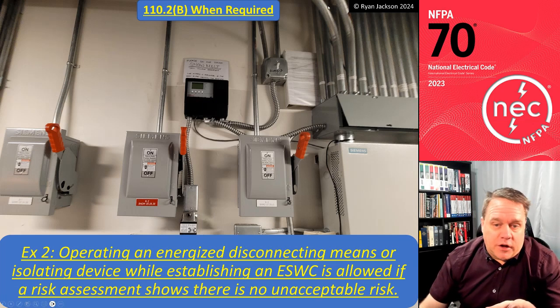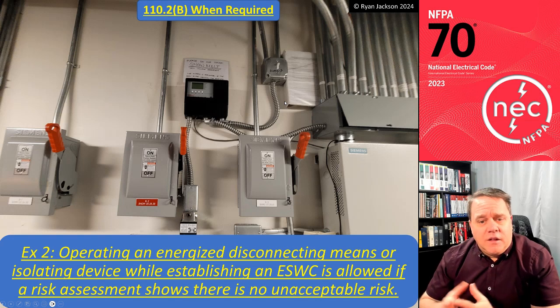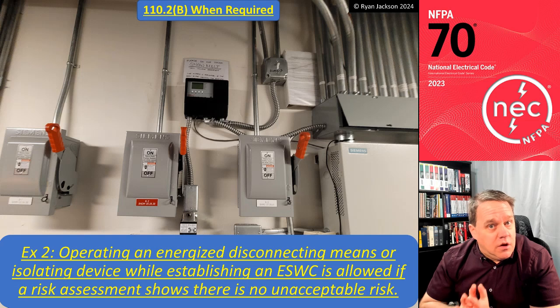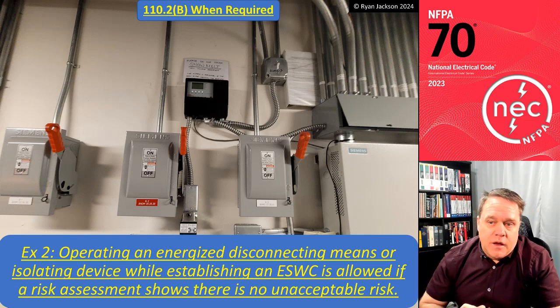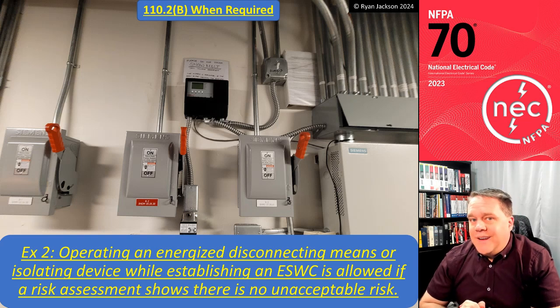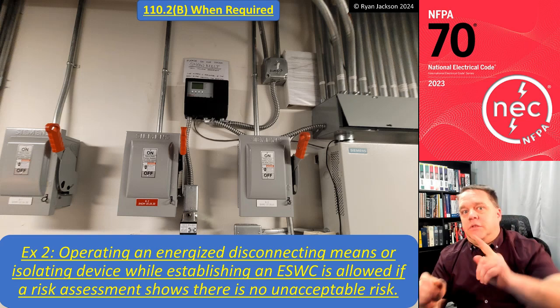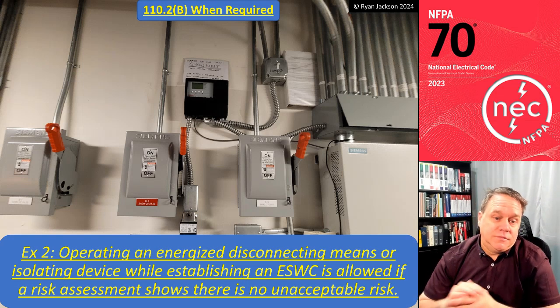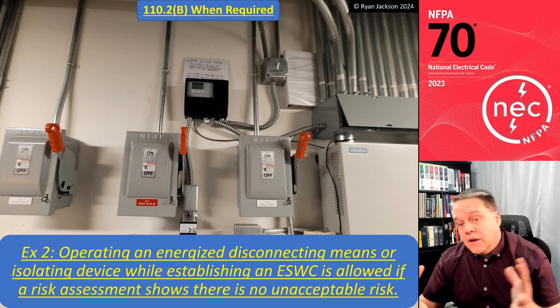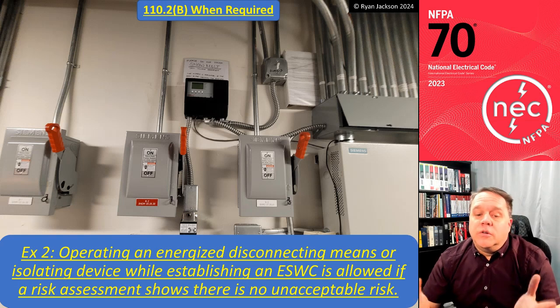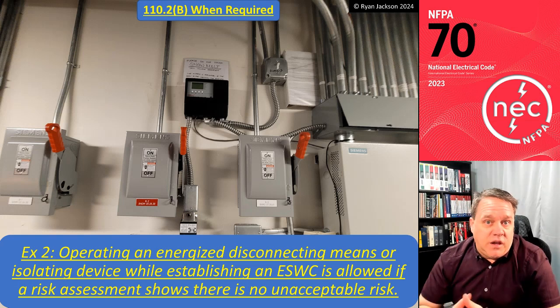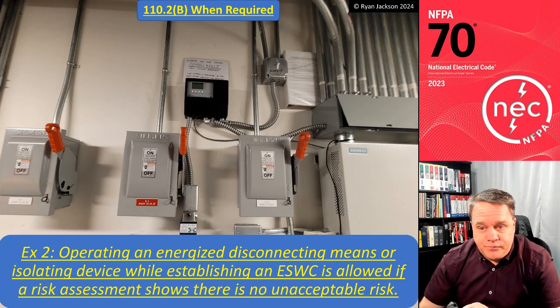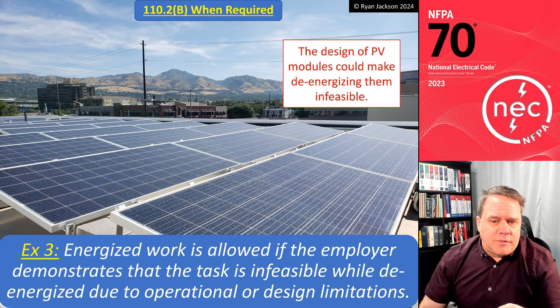I mean, first of all, let's look at that disconnect. That appears to be in normal operating condition, which means I can have normal operation of it. I can go up there and I can shut that thing off. What if it was not in a normal operating condition, but there's no disconnect upstream? Well, maybe it's the service disconnect. Well, if we do a risk assessment and we see that there's no unacceptable risk, then that might be something that we can do. We still have exception 3.